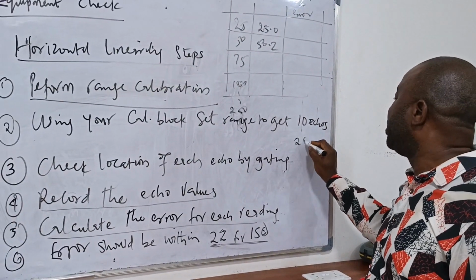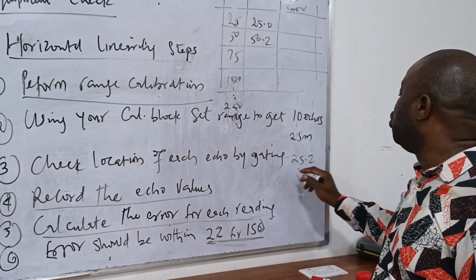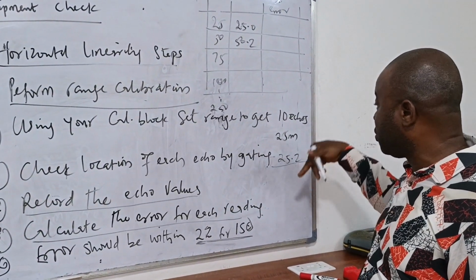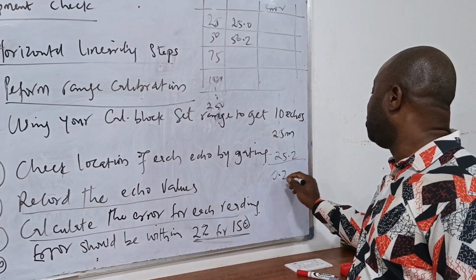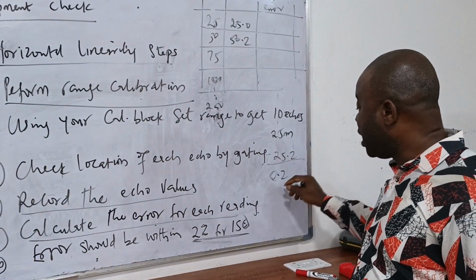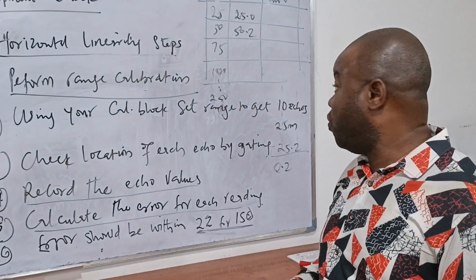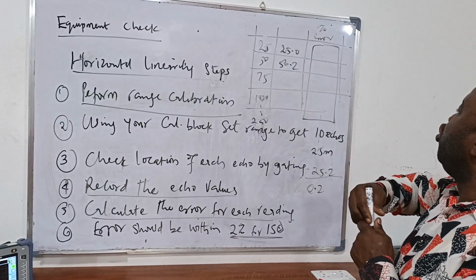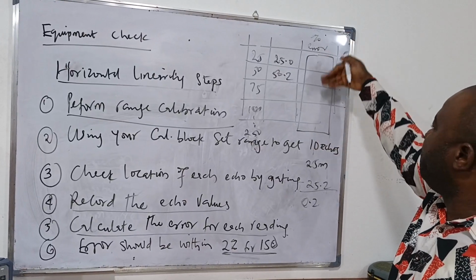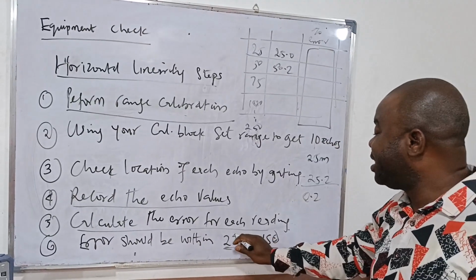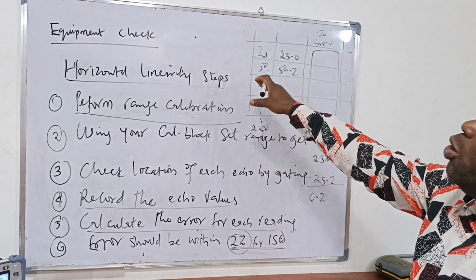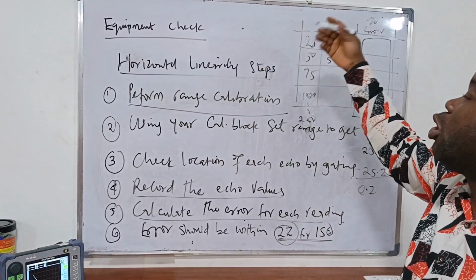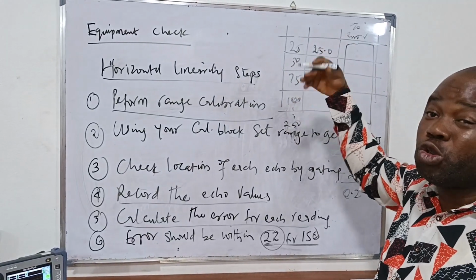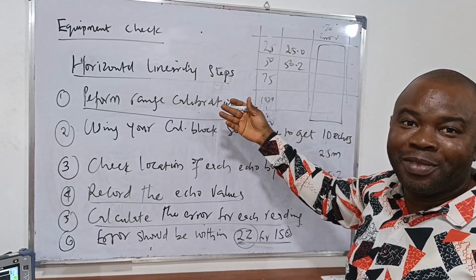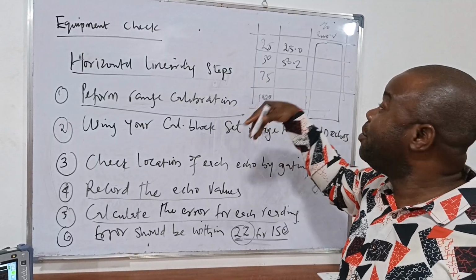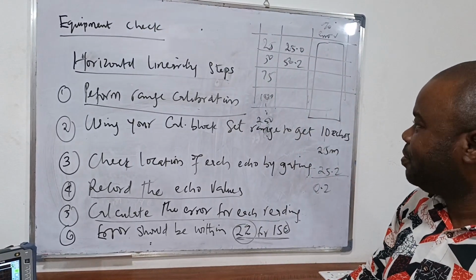If I'm expecting 25 mm and I get 25.2, my error is the reading I got minus the original reading, which is 0.2. Percentage error is the error divided by the original thickness, multiplied by 100 over 1. That is the mathematics. So you will check your error value. If any of these values is greater than 2%, it means that the horizontal linearity of the equipment is not correct, which means that machine should not be used for work because it's not going to give you accurate readings. That machine should be sent back for recalibration.